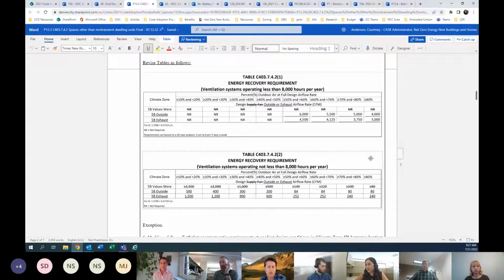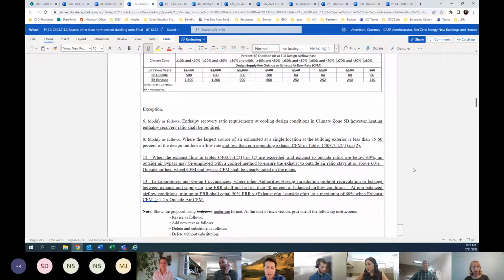And then scroll down a little bit further. We modified exception 6 just to clarify that in our climate zone, heating enthalpy recovery ratio is required. Then exception 8 has always been a bit of a problem, because what people would do is they would design 2 exhaust fans into a system that would then get them to have less than 75% exhaust and wouldn't have to do energy recovery, even though it's economical. So that just clarifies that. It does drop the threshold a little bit based on economics from 75 to 60%. And we have some supporting data down below.